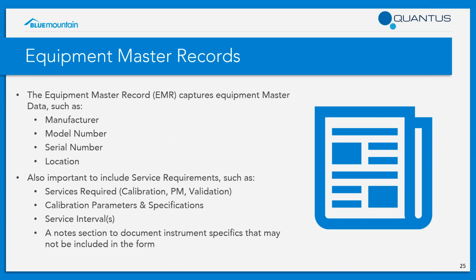So talking about equipment master records, what should typically be on these documents? We typically will see the boilerplate information: manufacturer, model, serial number, location. But it's also really important to include your service requirements, such as calibration or PM. It should include the parameters and specifications, or the test points and tolerances, that you're going to be using when you're testing that instrument. It should also include your service interval.